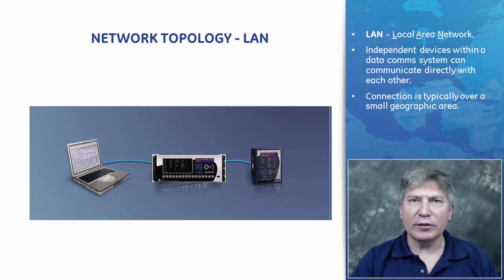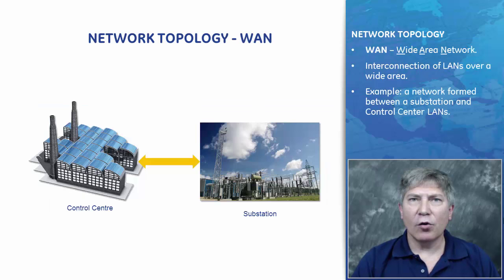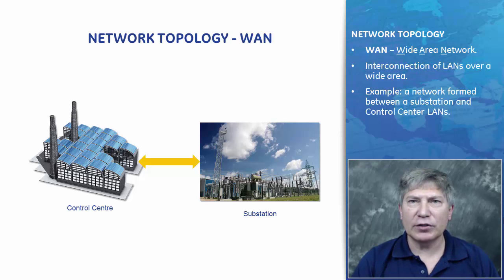LAN is an abbreviation for local area network. Typically, a LAN can be considered as all of the components that make up a data communication system which allows a number of independent devices to communicate directly with each other over a small geographical area such as a building. A WAN, or wide area network, is formed by the interconnection of LANs over a wide area. A typical utility example would be the network formed by the interconnection of the substation and control center's LANs, with distances ranging from a few to hundreds of kilometers.